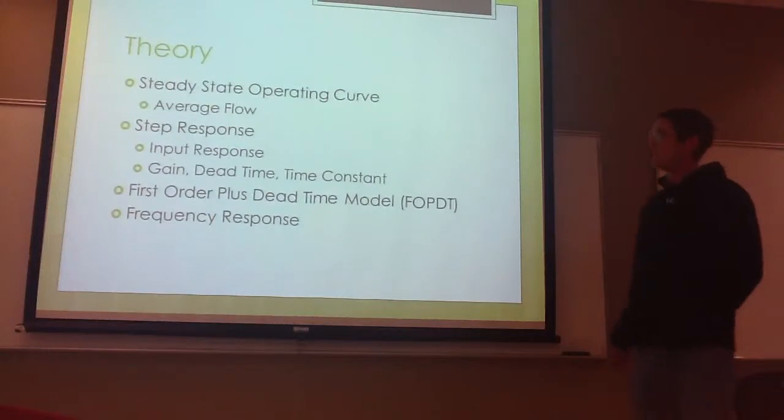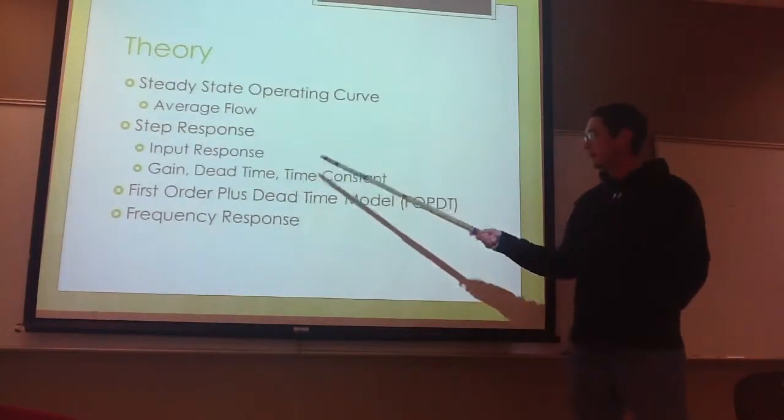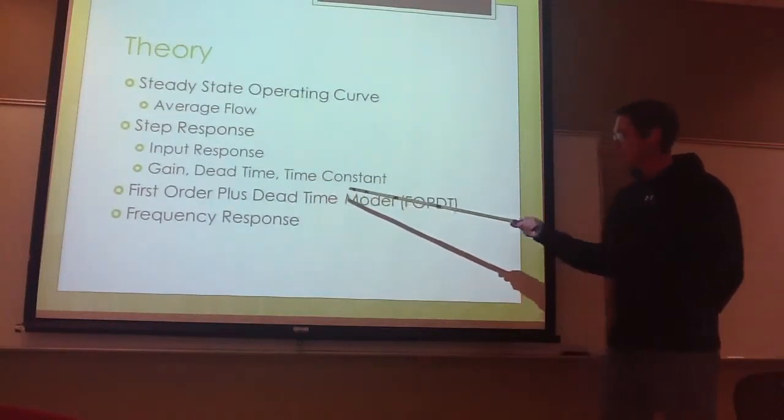And from that information, we get the gain, dead time, and time constant, which we can put into our FOPDT, first order plus dead time model, to better model our system. And then also the frequency response will give us the same information, but should be a little better.